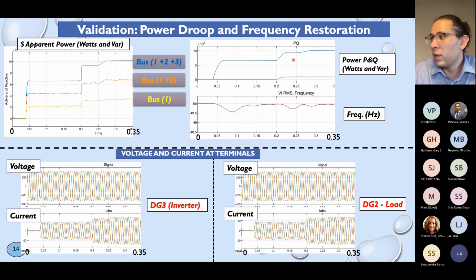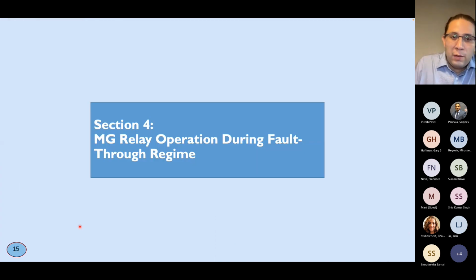But the important thing here is we are keeping the frequency as close to the nominal, and the voltage levels. In the two bottom figures, I'm showing the voltage and the current levels, as I mentioned before. So we can see the voltage is maintained during the different types of events, where we have the step load, we have the ramp load, and we can have a tap load in operation. So in the following section, I will talk about microgrid operation during a fault.